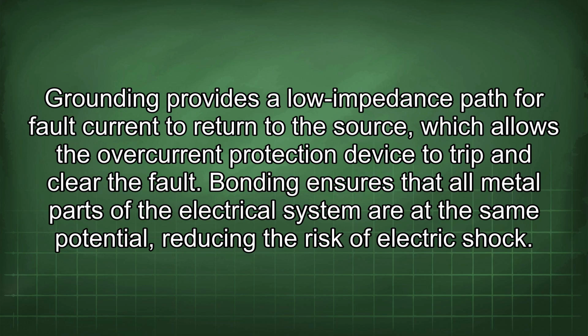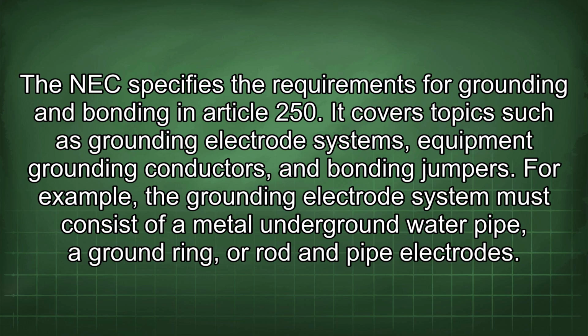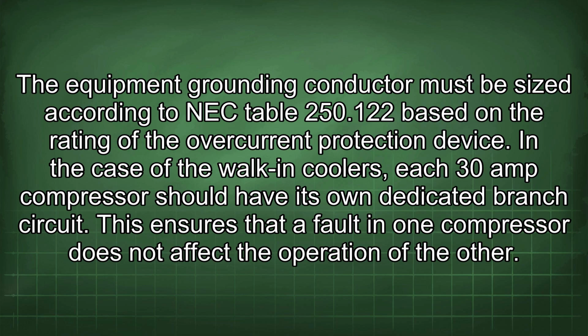Bonding ensures that all metal parts of the electrical system are at the same potential, reducing the risk of electric shock. The NEC specifies the requirements for grounding and bonding in Article 250. It covers topics such as grounding electrode systems, equipment grounding conductors, and bonding jumpers. For example, the grounding electrode system must consist of a metal underground water pipe, a ground ring, or rod and pipe electrodes. The equipment grounding conductor must be sized according to NEC Table 250.122 based on the rating of the overcurrent protection device.